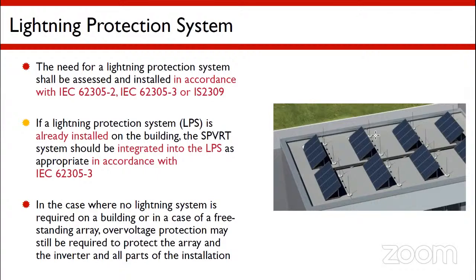So if you really want to look into the safety of the system, then the main factors are earthing and the lightning arrestor. The lightning arrestor will be employed on the rooftop area where the array has been arranged, and the zone of protection depends on the type of lightning arrestor and the height of the arrestor we are using. So I suggest in a normal plant, you can use one lightning arrestor of a medium level, which is able to cover a radius of 20-30 meters.